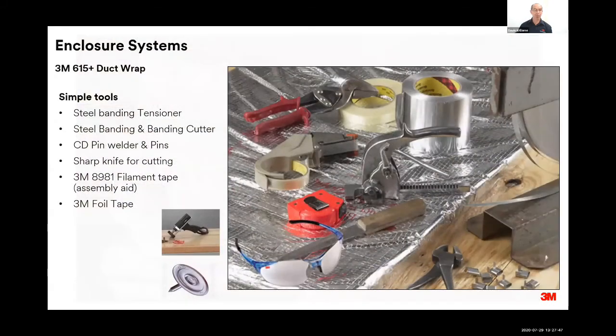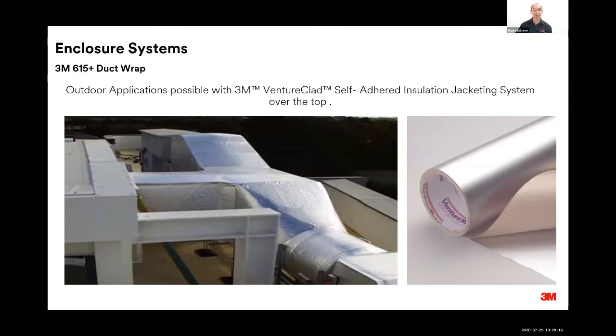The tools are very simple, typical of insulation lagging. Things like a cuphead pin welder and knives for cutting, and tapes for sealing up cut edges, for example. So it's fairly routine material, and there's not much in the way of capital outlay involved to be able to start wrapping the duct. We also have systems where ducts can be jacketed with our VentureClad self-adhered insulation jacketing, in the case where a duct may need enclosing construction and have portions of it on the exterior of the building.